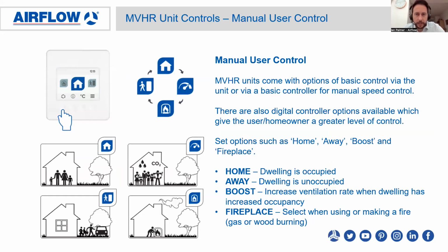Just on the controls, they can come with manual user controls. The MVHR units can come with options of basic control or digital controllers. Some of the settings available are home, away, boost, and fireplace. Home would mean when the dwelling's occupied, you'd have the ventilation system running on the home setting. Away, of course, is when the dwelling's unoccupied. Boost would be when you'd want to increase the ventilation rate, when perhaps you're having a party or you've got people around, so when the occupancy has increased. And fireplace is selected when you're using or making a fire or using any of the gas appliances.